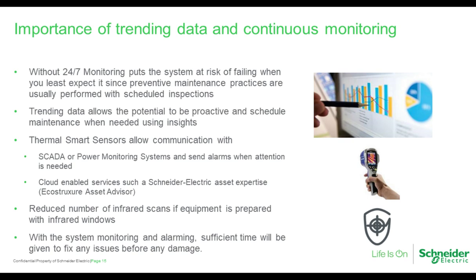With 24/7 monitoring, you can add additional maintenance practices that would be scheduled because you're seeing a trend of something that occurs. So now you can schedule outage time to take care of that. The trending data allows the potential to be proactive and schedule that maintenance when needed using insights from the different smart devices. Thermal sensors allow communication with SCADA or power monitoring systems and can send alarms when attention is needed. So we can set the parameters, and when we see a heat rise, we can send an alarm out so somebody can be proactive to a situation instead of reactive to a situation.